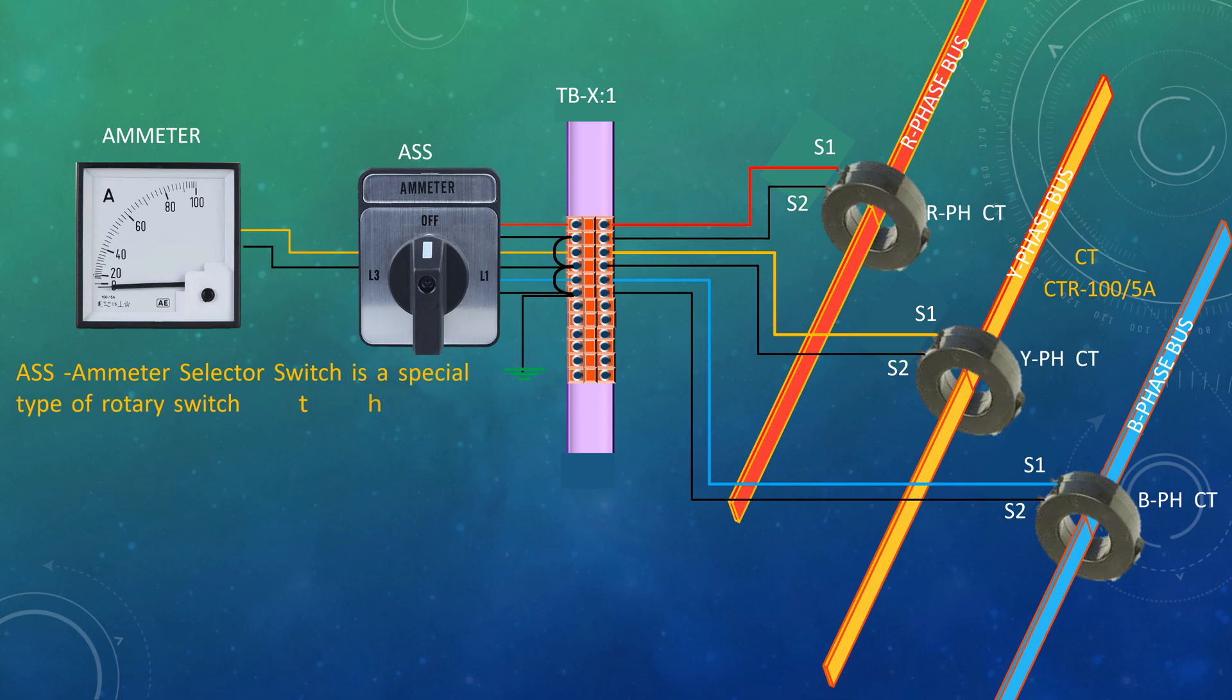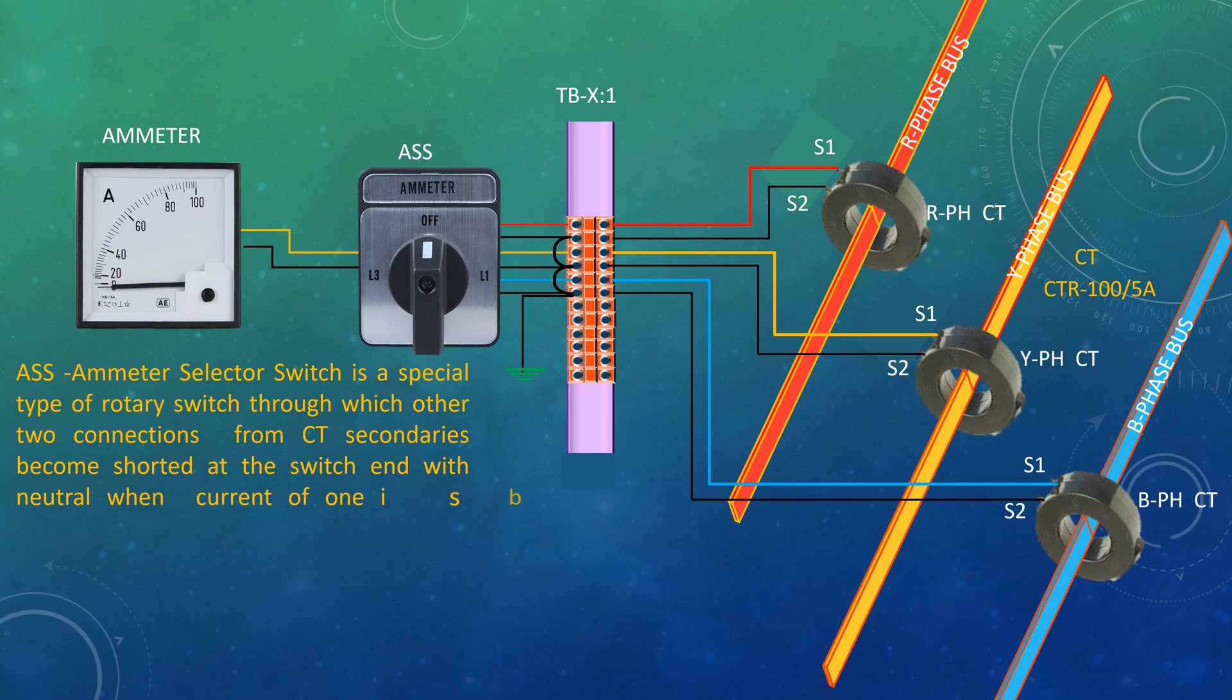Through which other two connections of CT secondaries become shorted at the switch with neutral when current of one line is being measured. This is done by rotation of knob of the selector switch so that secondary of any CT does not become open circuited.